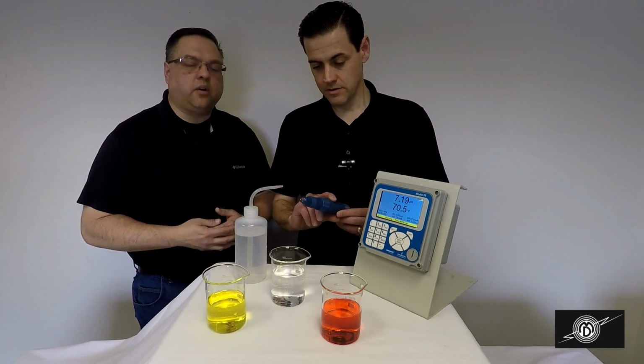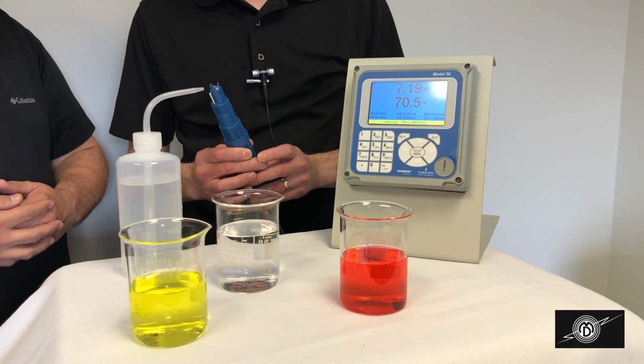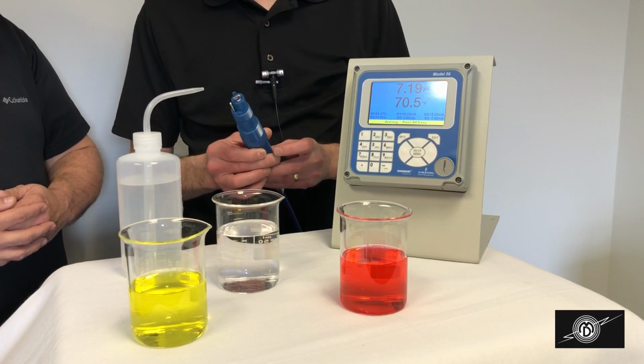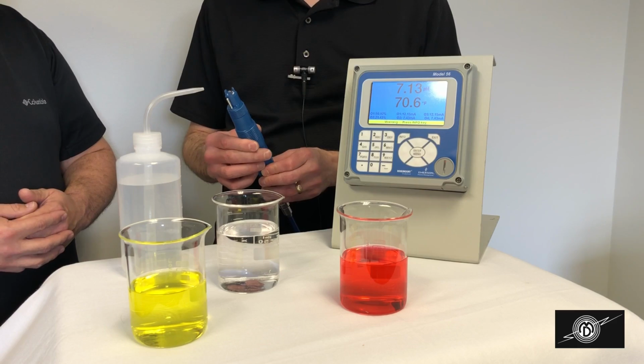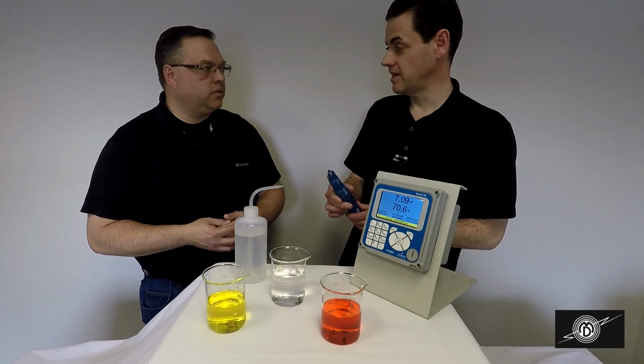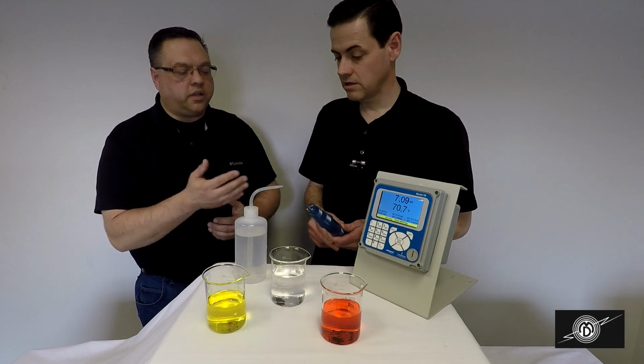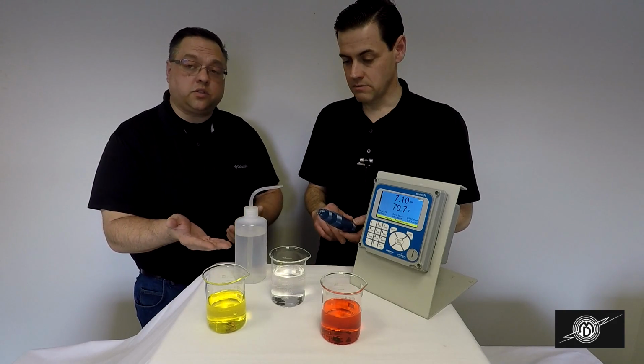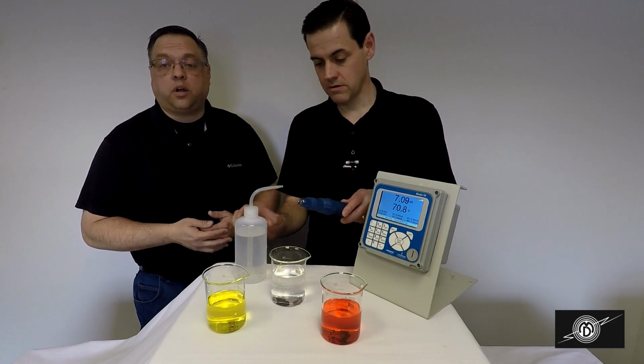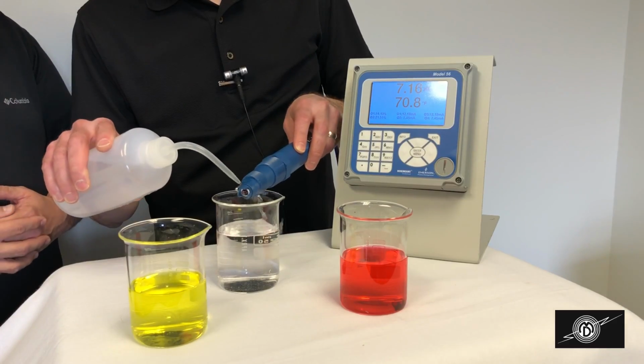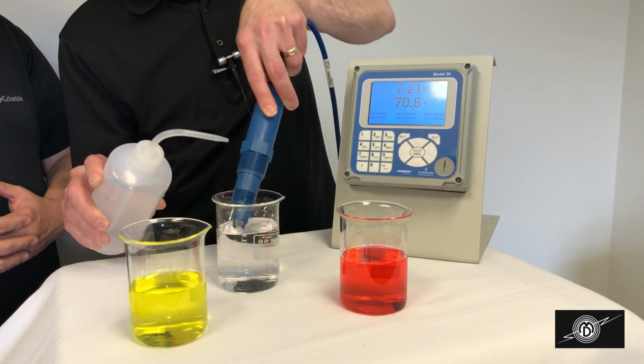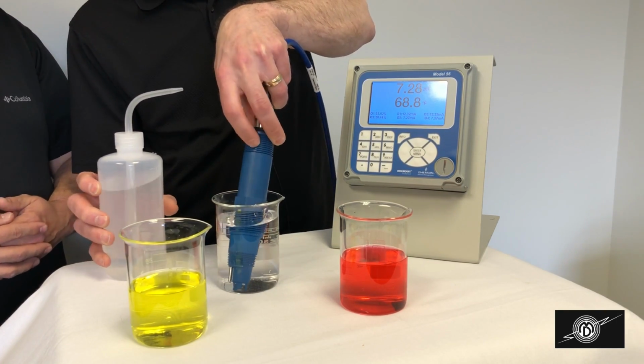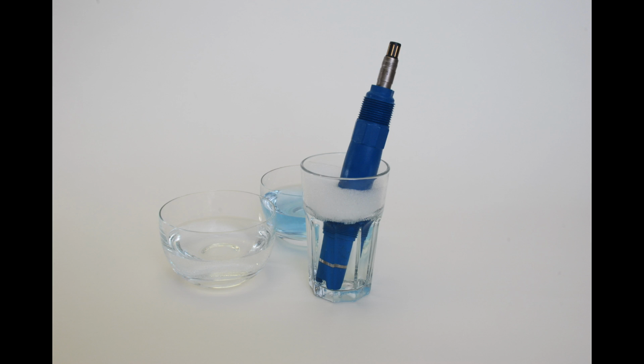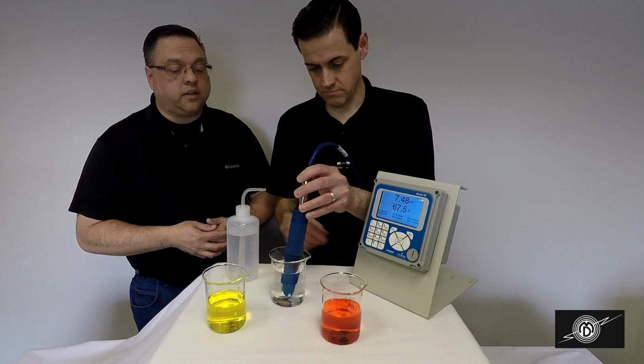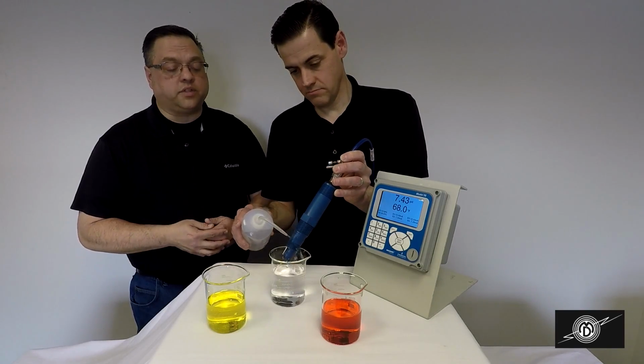Correct. You want to pull it out, clean and rinse it. Okay, now this is a newer sensor, so it looks pretty clean already. What if it were caked up with process material or something like that? How would you clean that? Then you want to clean it. Simplest is to use a rinse bottle with some clean DI water or tap water and rinse it off. If it's a little more aggressive, sludgy, cakey, oily, you want to take some dish soap and water and either rinse it off, scrub it off, or use a light toothbrush and clean that material off and rinse it.